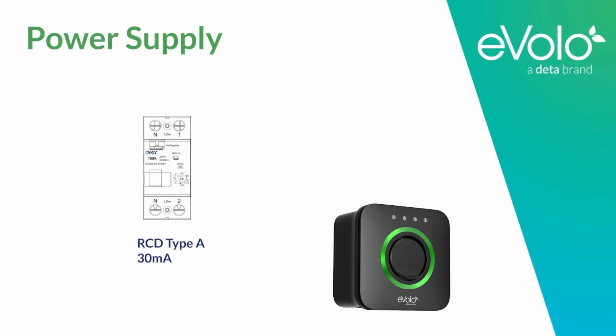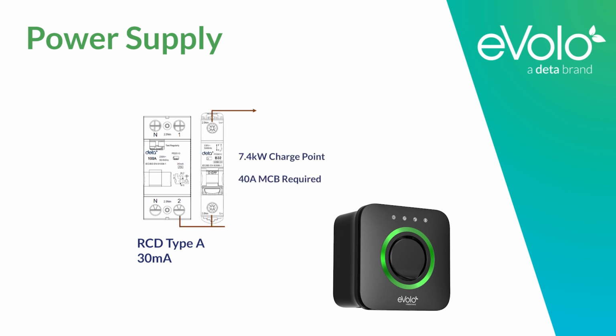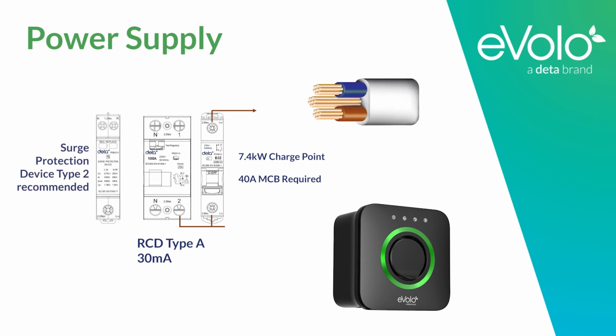Where it is intended that charge points will be operating at full capacity of 7.4 kilowatts, the MCB must be rated at 40 amps. An RCBO with the same characteristics is the ideal protective device, as it switches live and neutral to keep you and the end user safe. We recommend the installation has a Type 2 surge protective device fitted to protect the electronics within the charge point.